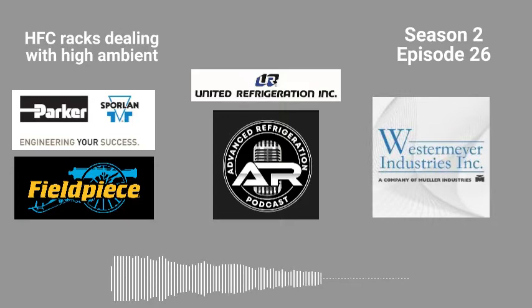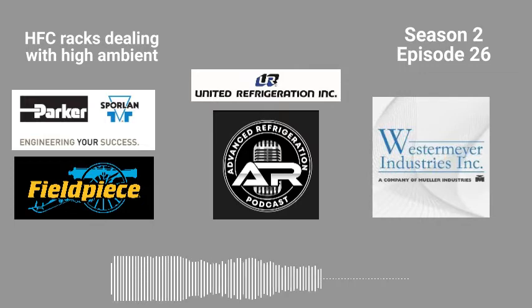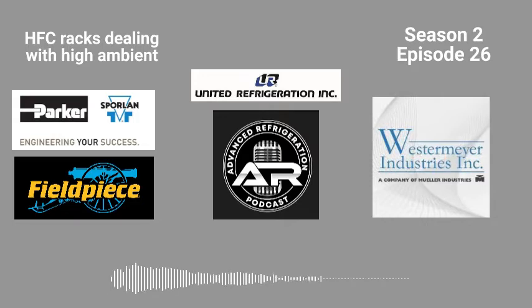Well, wait a minute. Are those the ones that are connected to the VFDs that are in the rack condensers? Or is that different? No, those things are junk. I can't wait to start retrofitting those things. No, I'm talking about like the EBM-Papst motors where they're all individual VFDs. The ones that are like 8 months out. Yeah, and like $9,000. Yeah, we replace those with standard motors.